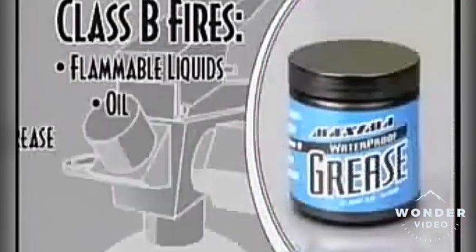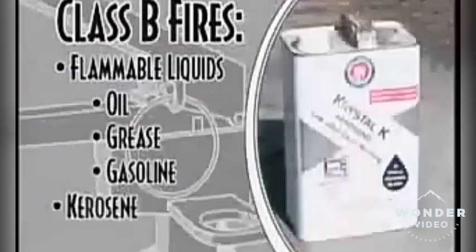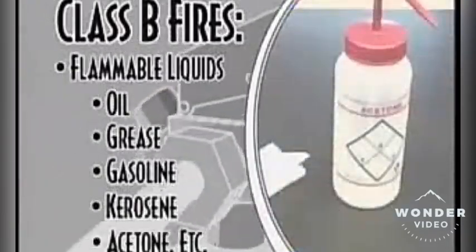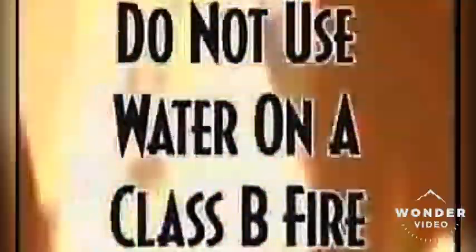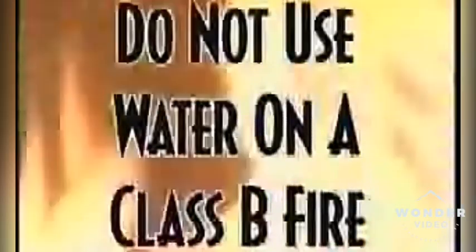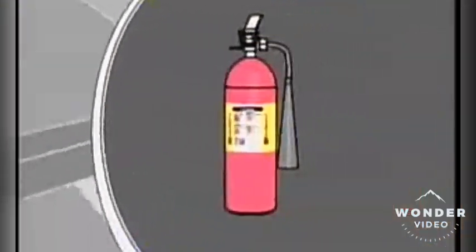Class B fires are fires of flammable liquids like oil, grease, gasoline, kerosene, and acetone. Using water on a Class B fire can spread the fire to a larger area, causing more damage or even injury. Class B extinguishers are labeled with the letter B inside a square and/or a picture of a burning gas can.